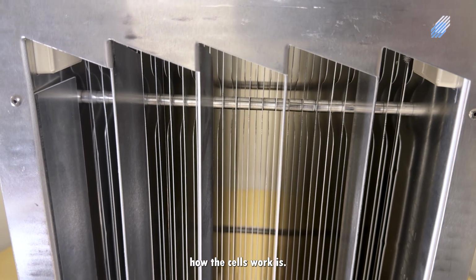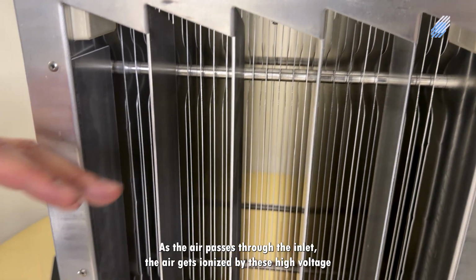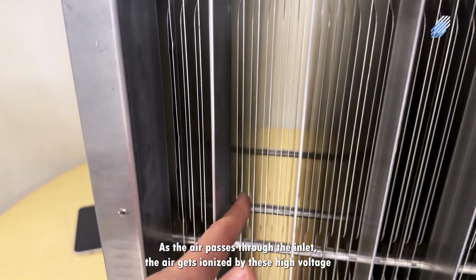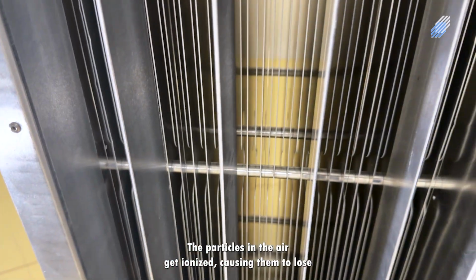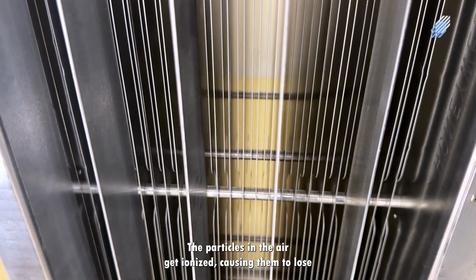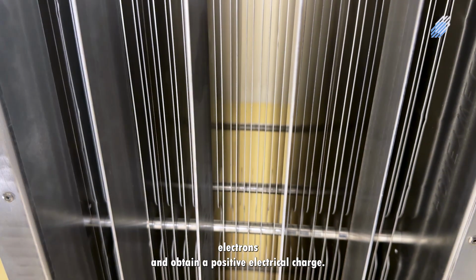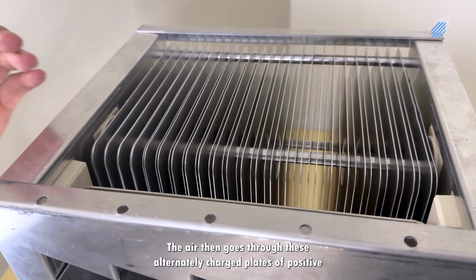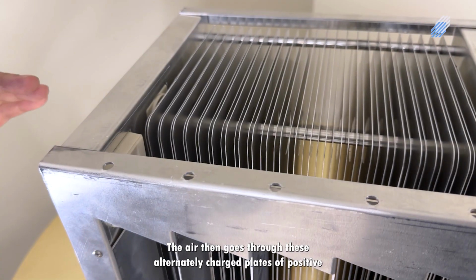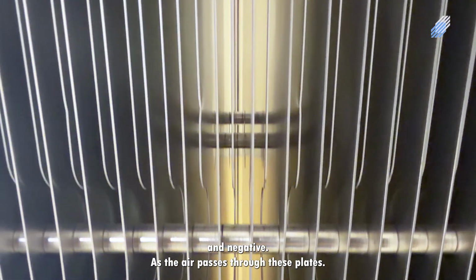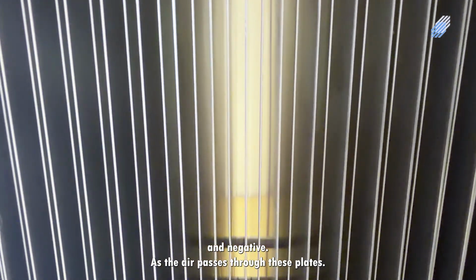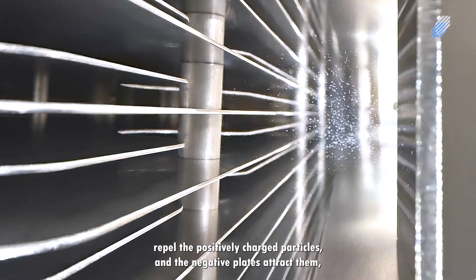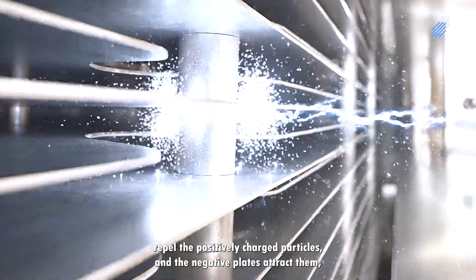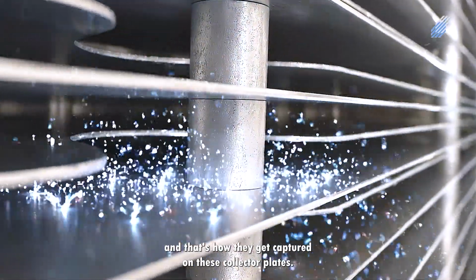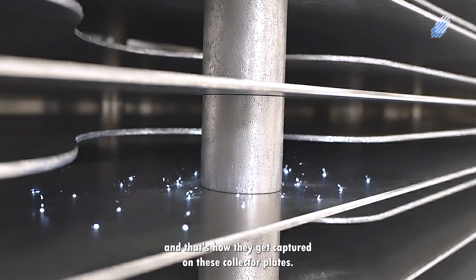How the cells work is as the air passes through the inlet, the air gets ionized by these high voltage ionizer wires. The particles in the air get ionized, causing them to lose electrons and obtain a positive electrical charge. The air then goes through these alternately charged plates of positive and negative. As the air passes through these plates, the positively charged plates repel the positively charged particles and the negative plates attract them. And that's how they get captured on these collector plates.